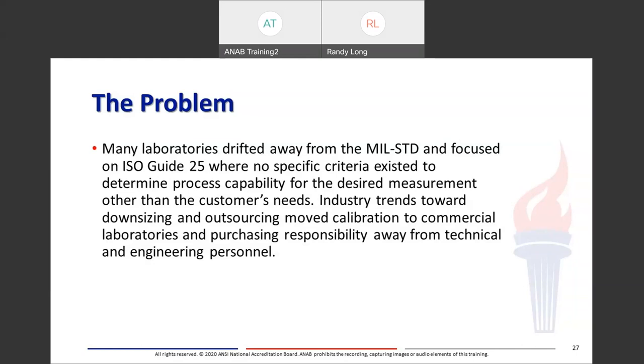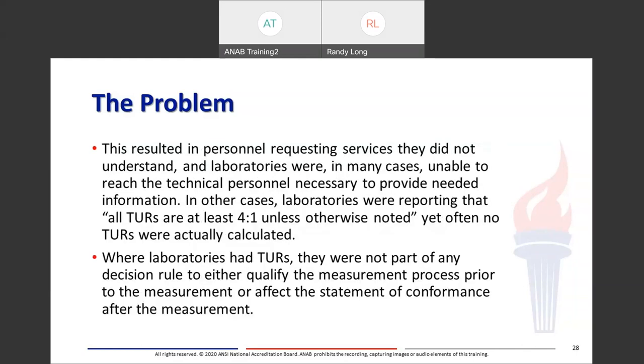MIL-STD 45662 was rescinded in 1994 and Z540-1 was issued. Many United States folks gravitated to the new standard, seeing perceived weaknesses in ISO Guide 25, as it largely addressed things in MIL-STD 45662 that were not in Guide 25. The popularity of laboratory accreditation to ISO Guide 25 in the late 90s in response to QS 9000 revision 3 began many new discussions on uncertainty and measurement, and confusion abounded. Many laboratories drifted away from the MIL-STD and focused on Guide 25, where there are no specific criteria to determine process capability other than customer needs, and industry trends toward downsizing and outsourcing moved calibration to commercial laboratories — resulting in personnel requesting services they did not understand. Laboratories were, in many cases, reporting that all TURs are at least 4-to-1 unless otherwise noted, yet often no TURs were actually calculated.